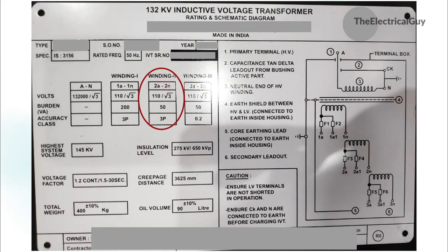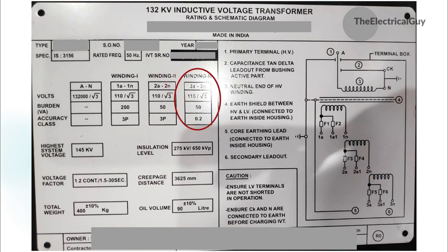Winding 2 is marked as 2A and 2N. It has a secondary voltage of 110V/root 3, a rated burden of 50VA, and an accuracy class of 3P. Winding 3 is marked as 3A and 3N, with a secondary voltage of 110V/root 3, a rated burden of 50VA, and an accuracy class of 0.2. So in total there are 2 protection windings and 1 metering winding.